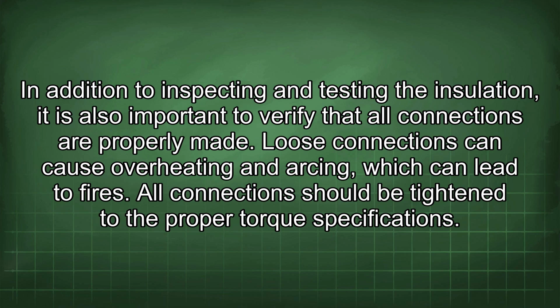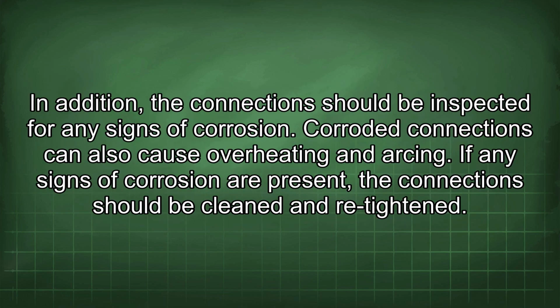In addition to inspecting and testing the insulation, it is also important to verify that all connections are properly made. Loose connections can cause overheating and arcing, which can lead to fires. All connections should be tightened to the proper torque specifications. In addition, the connections should be inspected for any signs of corrosion. Corroded connections can also cause overheating and arcing. If any signs of corrosion are present, the connection should be cleaned and retightened.